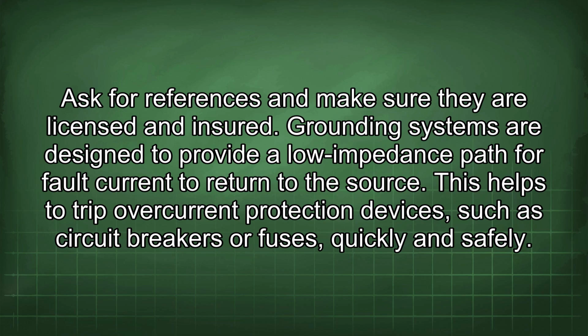Grounding systems are designed to provide a low impedance path for fault current to return to the source. This helps to trip overcurrent protection devices, such as circuit breakers or fuses, quickly and safely.